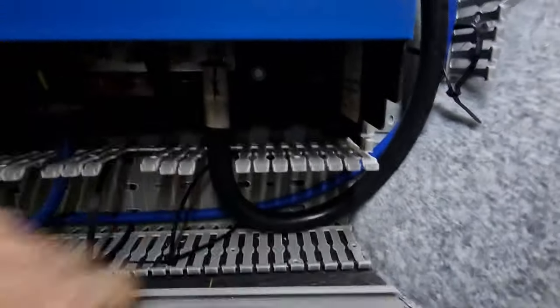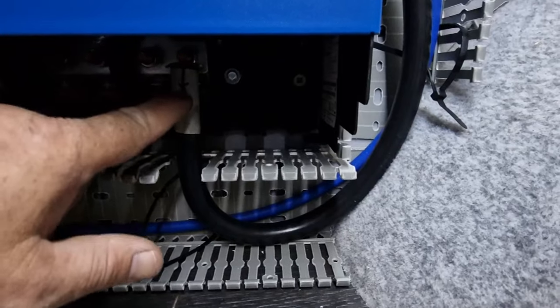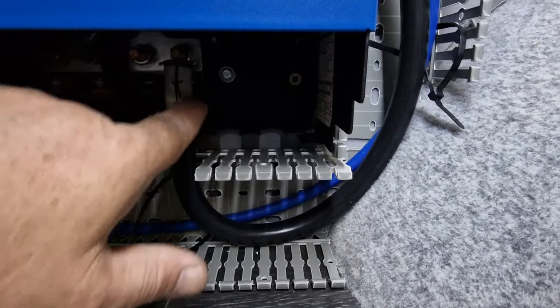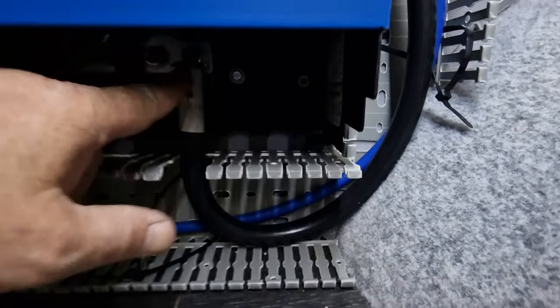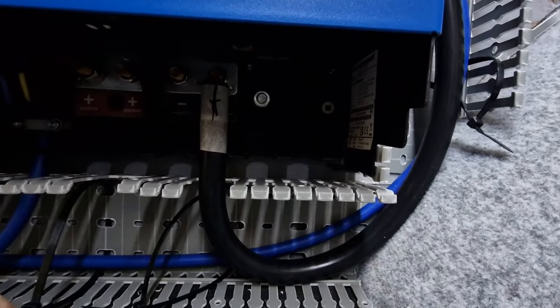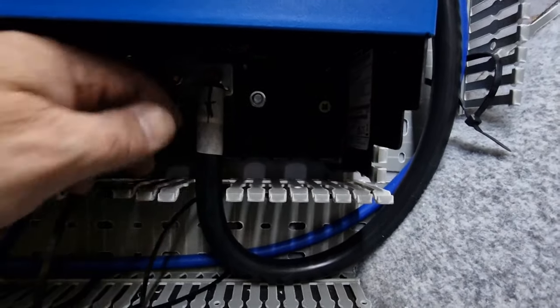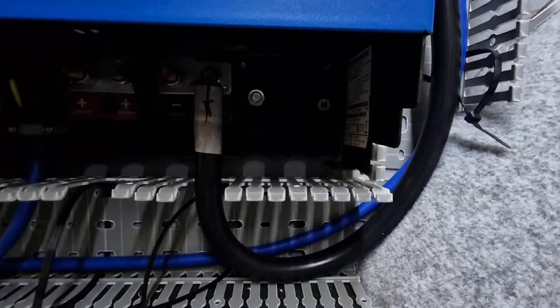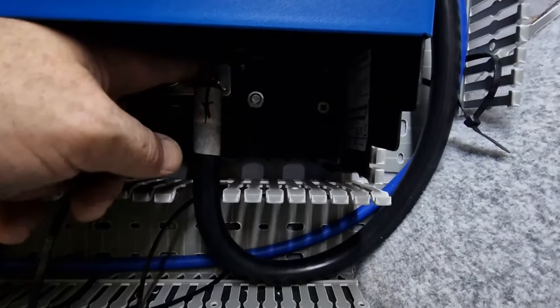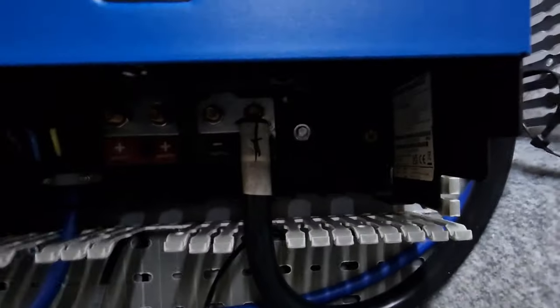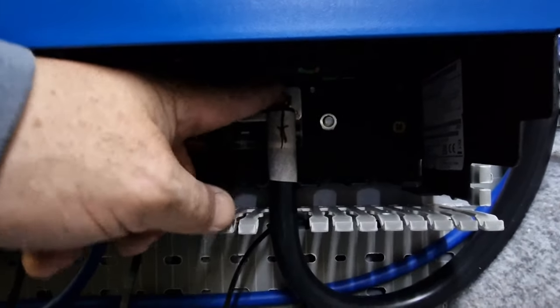The reason for mocking up the cables is because when you start running them into position, this cable will want to sit where it wants to sit, and there's not a lot you can do about that. But if you crimp your ends before you actually do this, you could end up with it pointing sideways, twisted, not aligning, and then you'd have to go back and make the cable off again, or try to force it into somewhere it doesn't want to go, putting pressure on the terminals, which would over time probably end up fatiguing these.